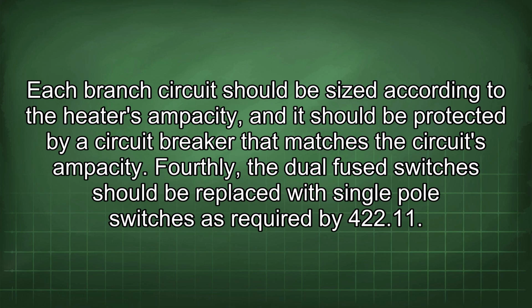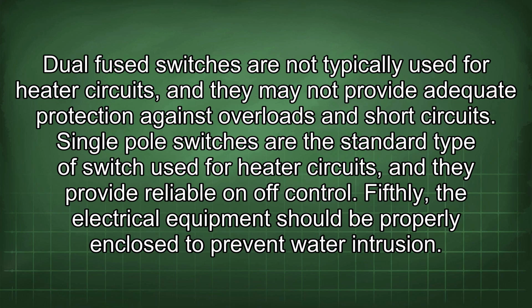Fourthly, the dual fuse switches should be replaced with single pole switches as required by 422.11. Dual fuse switches are not typically used for heater circuits, and they may not provide adequate protection against overloads and short circuits. Single pole switches are the standard type of switch used for heater circuits, and they provide reliable on-off control.